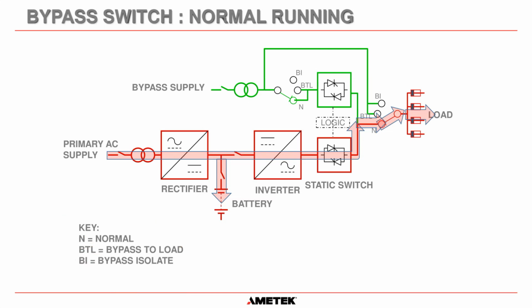Now remember, here's the switch. Here's one set of contacts on the switch, and here's the other set. Okay, so they are drawn here, two sets of contacts. Now remember, this is the mechanical switch. In this circumstance, this is usually a rotating switch. You move it from normal position to bypass to load, and then from bypass to load to bypass isolate. So it is an actual mechanical switch that does have moving parts.